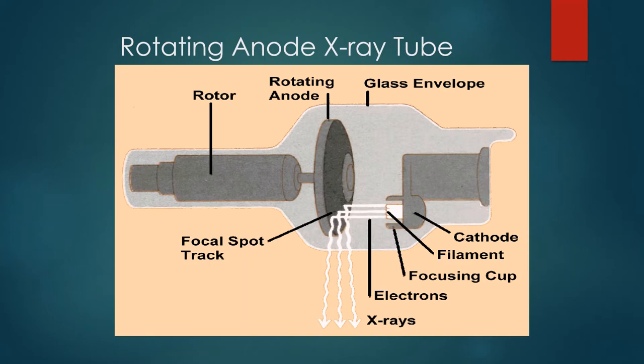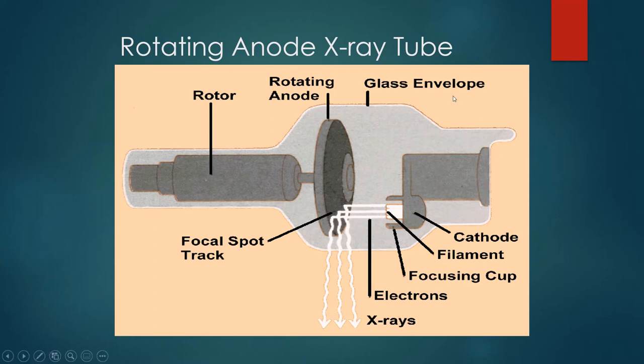The anode rotates — it's not actually necessary for creating x-rays, but rotation prolongs the life of the equipment and makes for more efficient x-ray creation. It has a rotor powered by electromagnetic induction, similar to the motors in an electric car. All of this action inside the glass envelope is done inside a vacuum, meaning all of the atmosphere has been removed from the inside of the envelope.